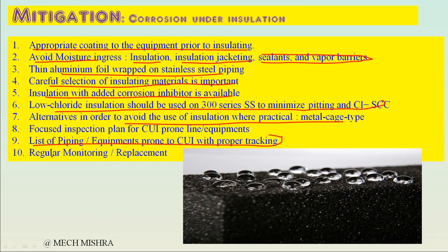Then regular monitoring and replacement should be a practice. We need to check whether some insulation is damaged. Then as per API guideline, we have to open a certain amount of insulation. If we find damage and CUI, then we have to open the insulation further to check. So that's how you have to prepare a strategy to fight this hidden threat and to avoid failure.